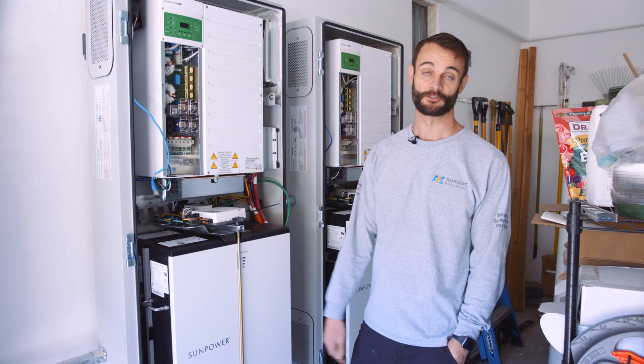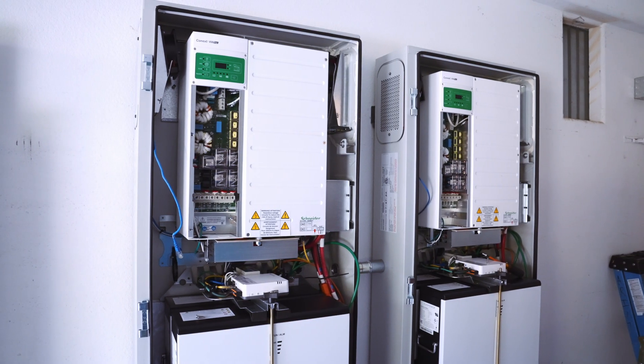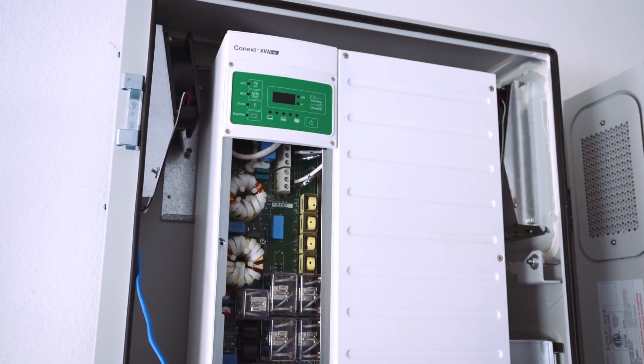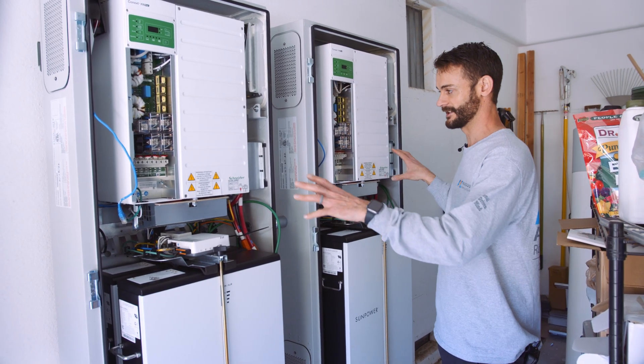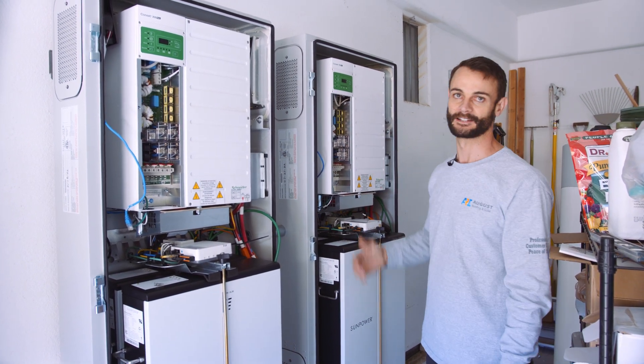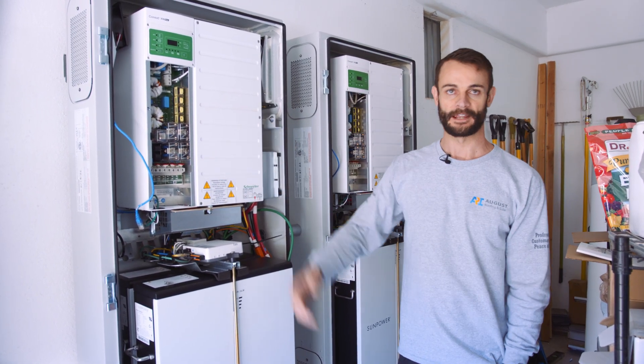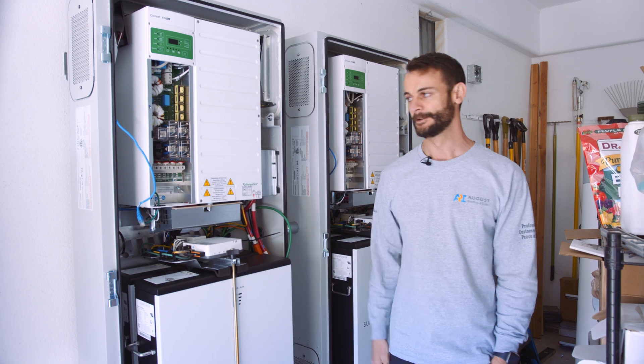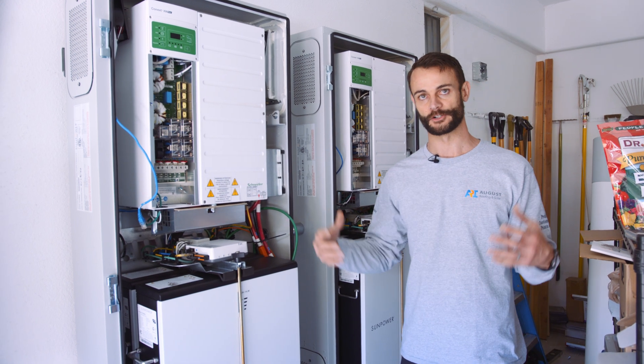Together the two cabinets make 26 kilowatt-hours, so he'll be able to go for quite a while on his battery backup system. These are the battery inverters, and SunPower continually brings updates in. In the last few months they've updated their system to have two battery inverters. What that does is make the system much more powerful — you can have a 70 amp breaker where before you were only able to put a 35 amp breaker as your largest breaker. That's one of the benefits of having two inverters along with having a larger storage capacity.